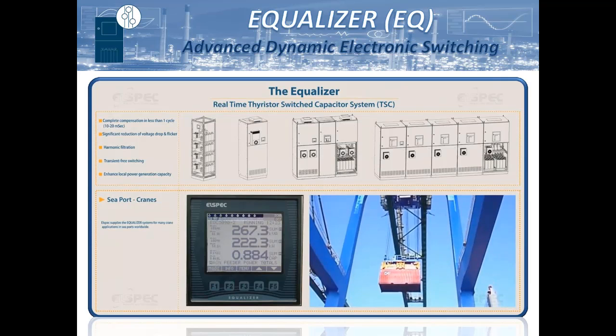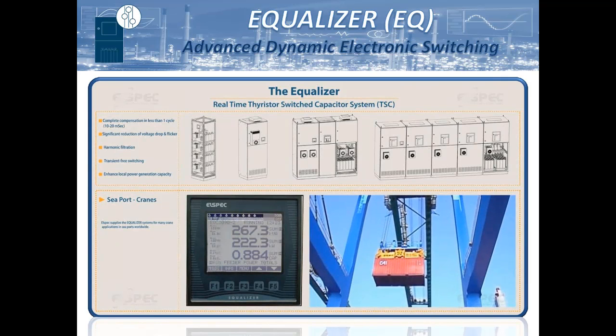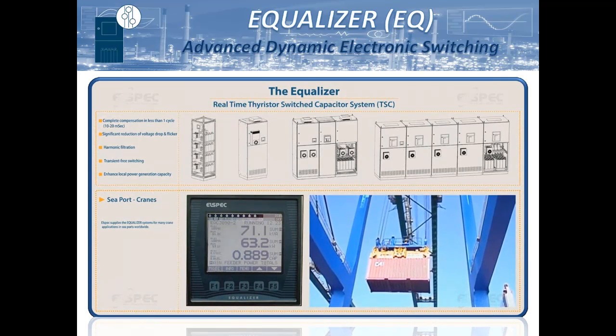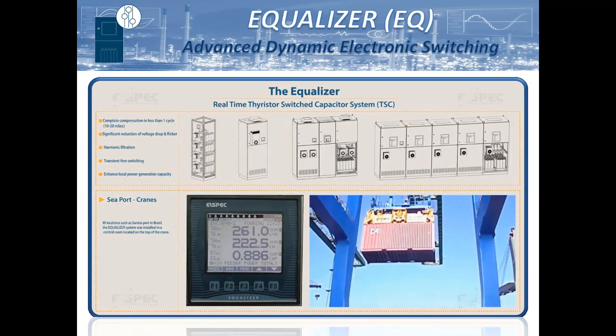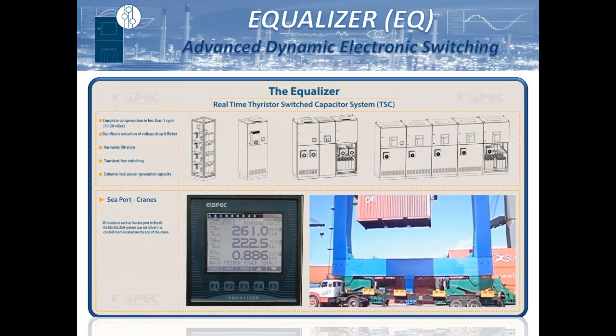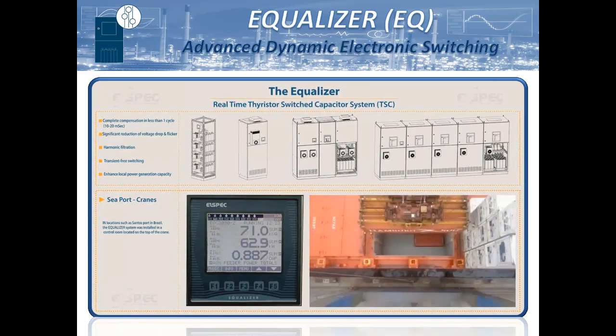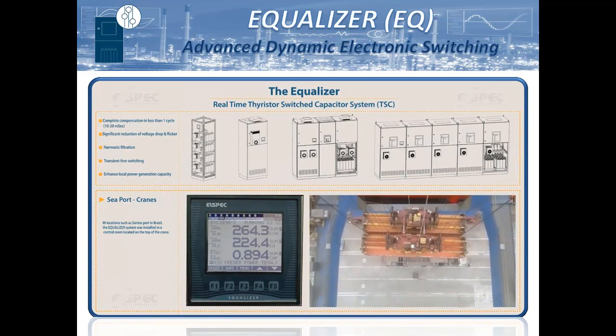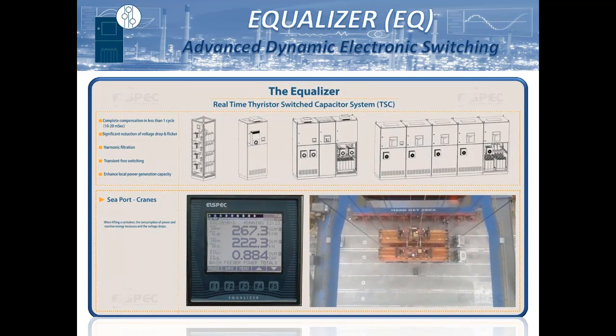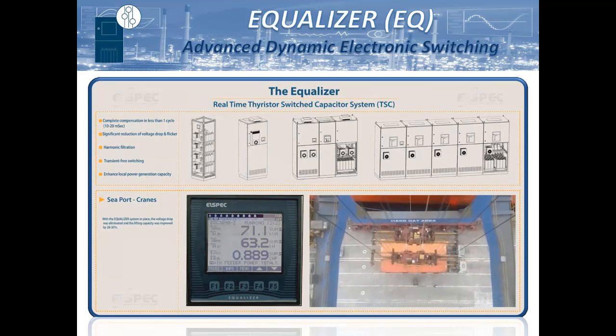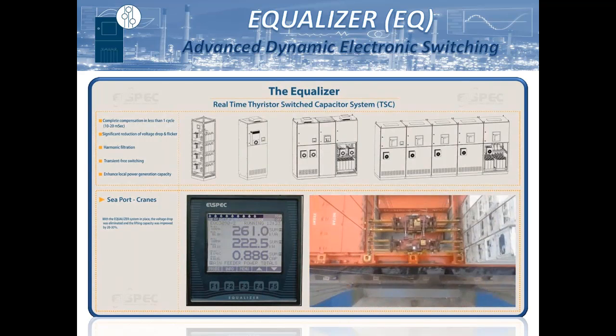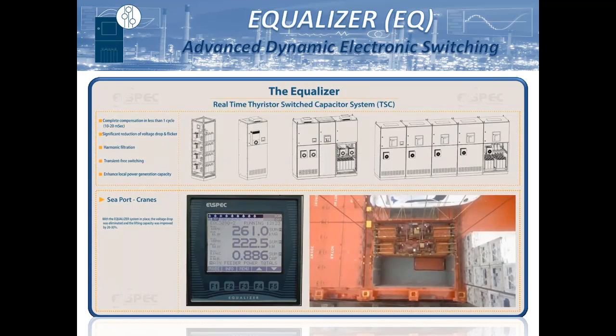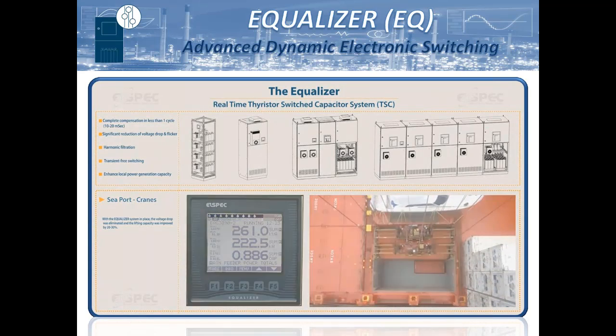ELSPEC supplies the equalizer systems for many crane applications in seaports worldwide. In locations such as Santos Port in Brazil, the equalizer system was installed in a control room located on the top of the crane. When lifting a container, the consumption of power and reactive energy increases and the voltage drops. With the equalizer system in place, the voltage drop was eliminated and the lifting capacity was improved by 20 to 30%.